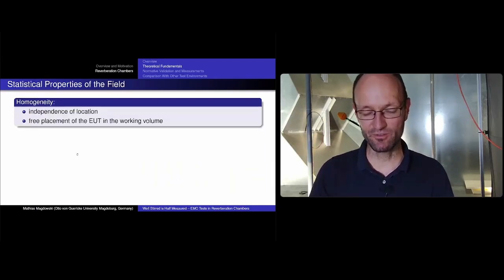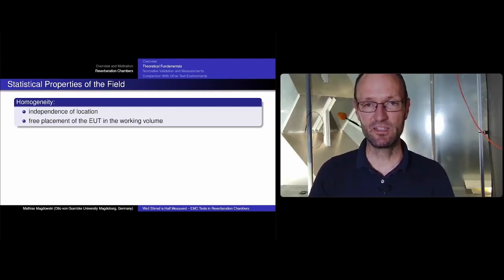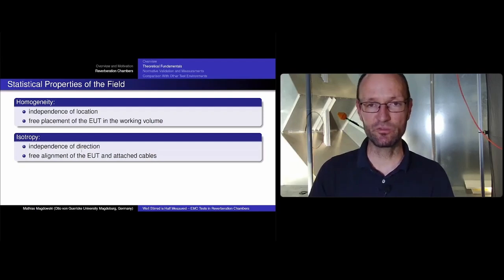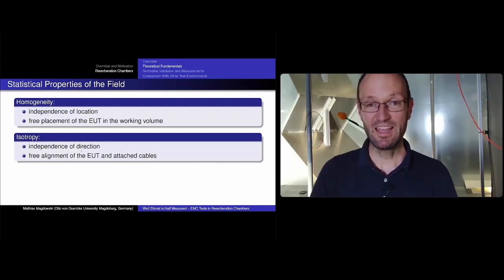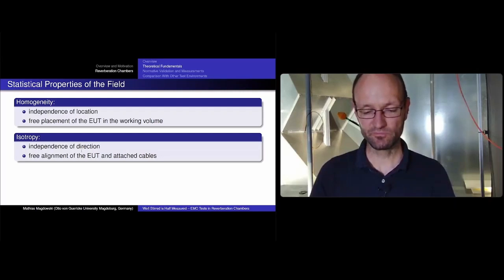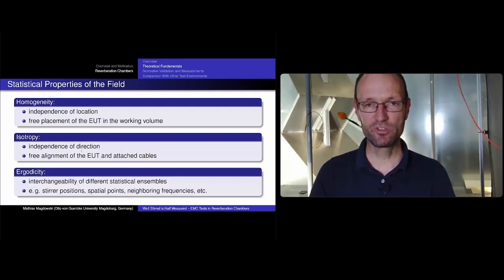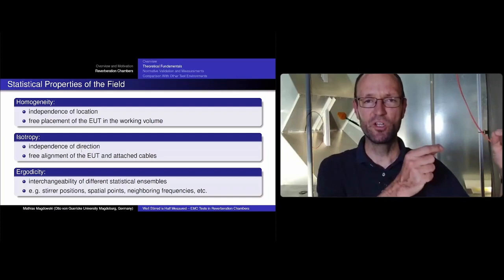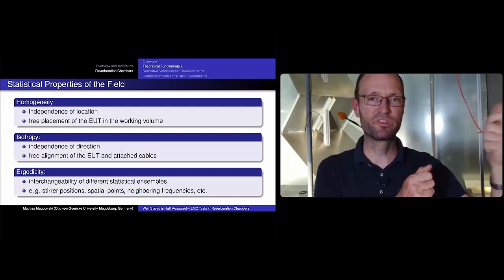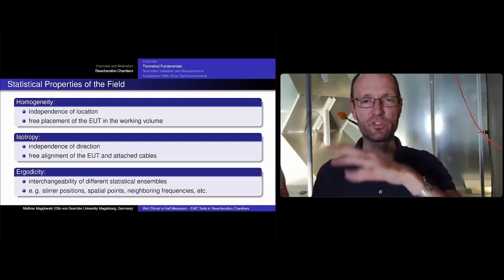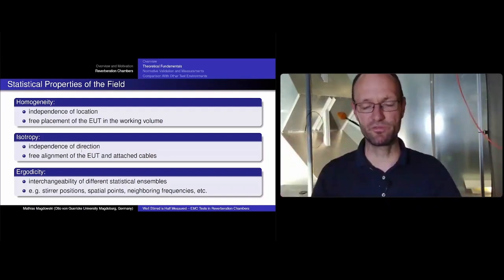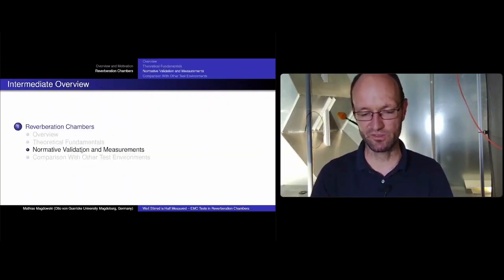The statistical properties of the reverberation chamber field are: first, statistically homogeneous — it doesn't matter where we place the device under test; second, isotropic — it doesn't matter in which direction the device and cables are oriented; and third, ergodic — meaning statistical ensembles are interchangeable, so measuring the field for different stirrer positions and averaging is equivalent to measuring the field at different spatial positions.